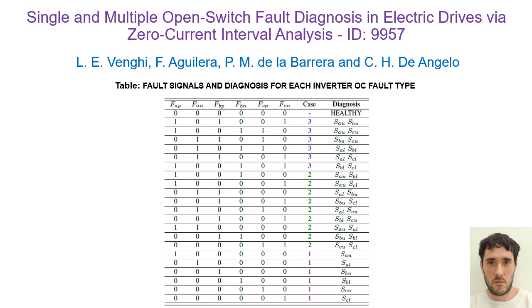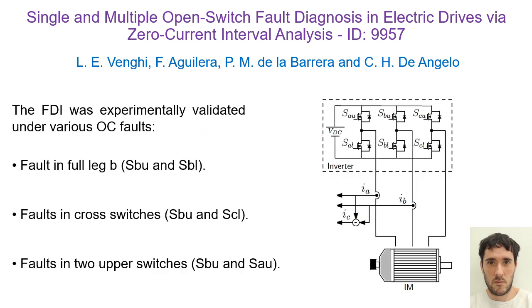The final fault isolation is performed according to the table, which details the diagnosis for all fault cases. The proposed method was experimentally validated under various fault conditions, including full leg open circuit faults, crossed switch faults, and simultaneous open circuit faults of the two upper switches.